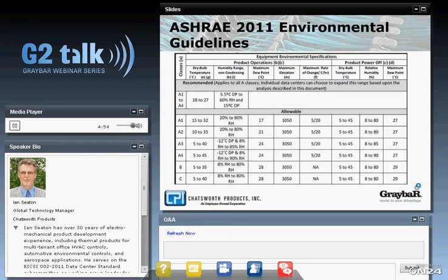So that's been corrected with the 2011 paper, which provides tables and equations that allow you, for your area, to make a calculation on what will be the reliability impact on your equipment to operate at different temperatures from what we call the X factor temperature, which is 24/7 at 68 degrees.